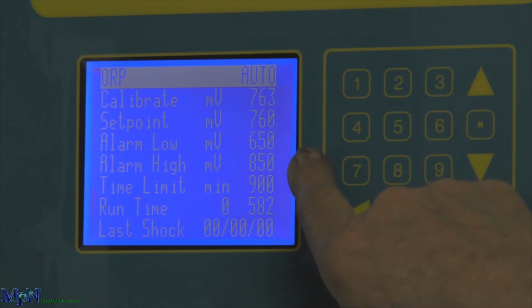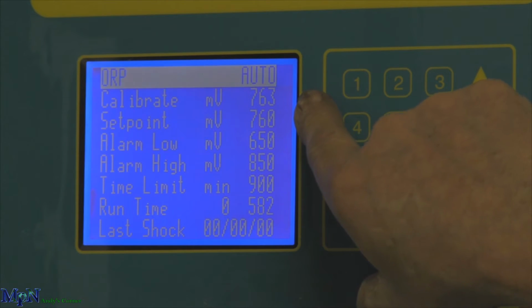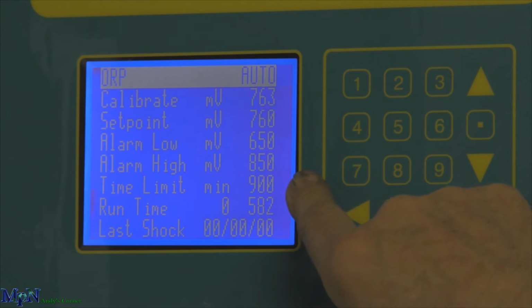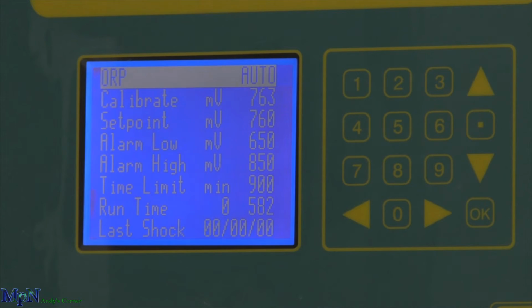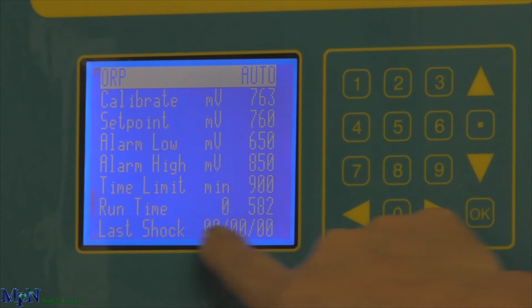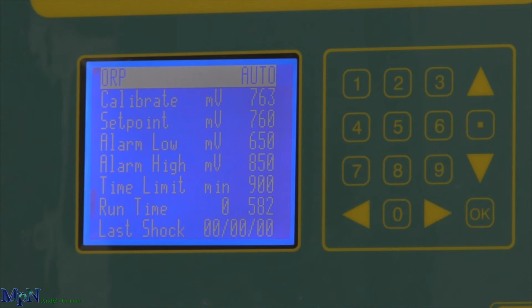We put in a safety low alarm. On this one it's 650, which for pH would be 7.0. High alarm is 850, which is a little bit above what we're running on a normal mode, only because if you have to shock the pool, you won't go into any lockout alarms. We have a time limit that lets you pump only for so much continuous time before it'll shut off. You can go anywhere from 4 hours, 6, 8, depending on what kind of demand you have on the water. And we have the run time, which counts up every time it turns on. It'll start counting up to your safety timers.